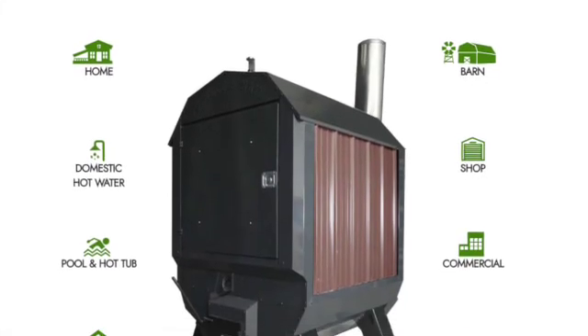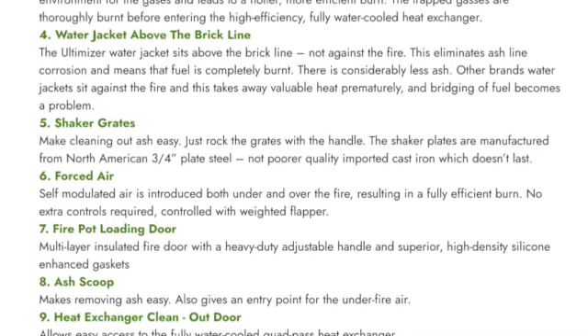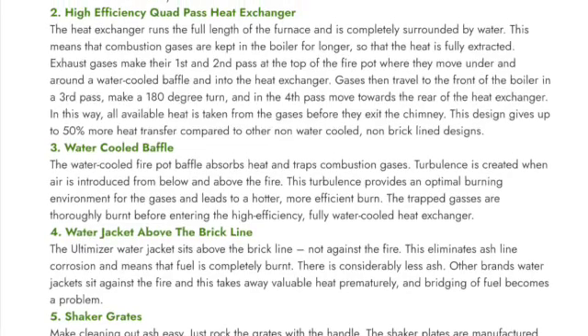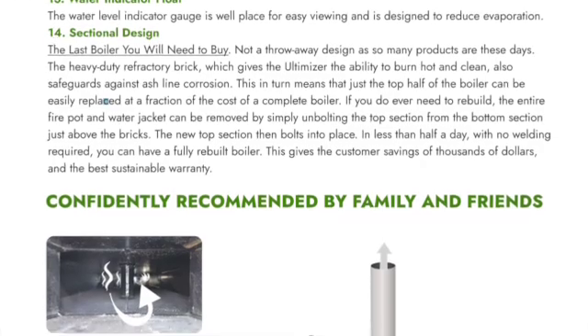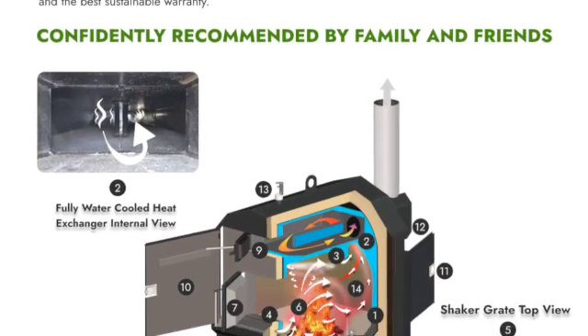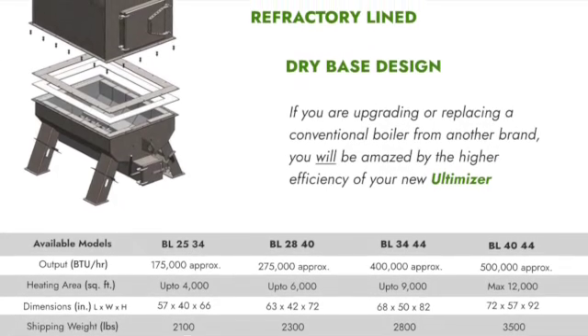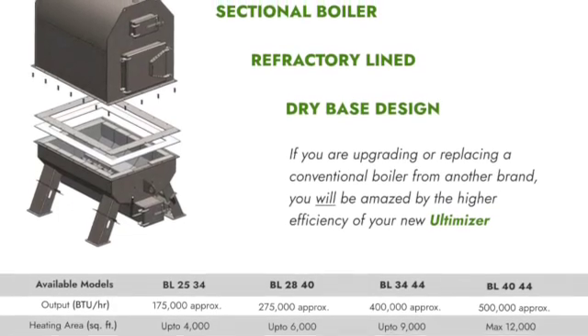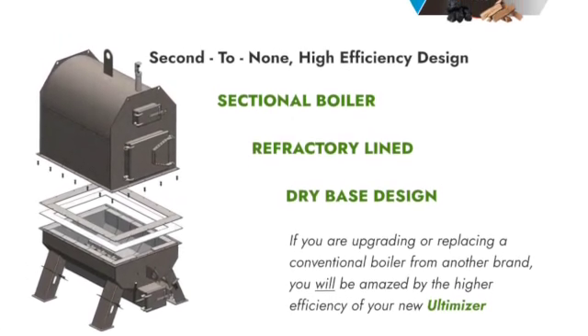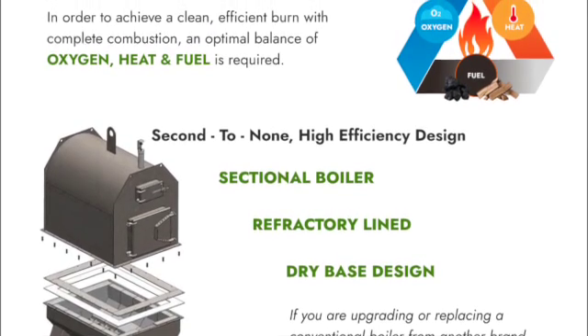The key features of this stove are: the refractory-lined base, which eliminates the ash-line corrosion that happens in a lot of stoves; combustion air coming up through the bottom of the coals; the heat exchange chamber at the top of the stove where gases are rerouted and kept in the stove longer to get maximum heat out of the gas exchange; and finally, the entire top of the stove can be taken off and replaced — the part that has the water in it is completely removable, making it very easy to recondition. This could be the very last stove you ever have to buy.